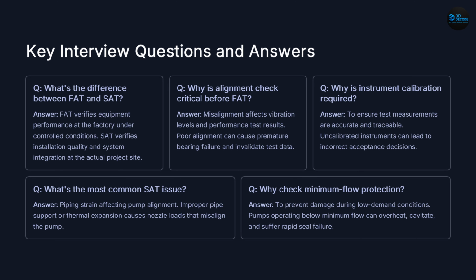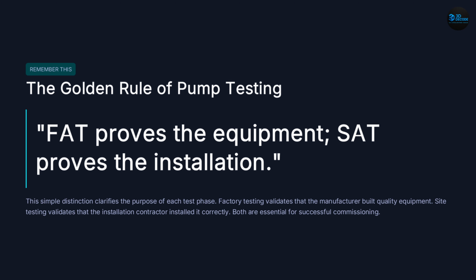Next, the golden rule of pump testing. Let's finish with the most important statement in the entire presentation. FAT proves the equipment. SAT proves the installation. That's it. Simple. But if FAT fails, the equipment may have a manufacturing issue. If SAT fails, the installation may have a site integration issue. Understanding this distinction changes how engineers approach troubleshooting, because it separates equipment performance from installation performance, and that separation often leads directly to the root cause.